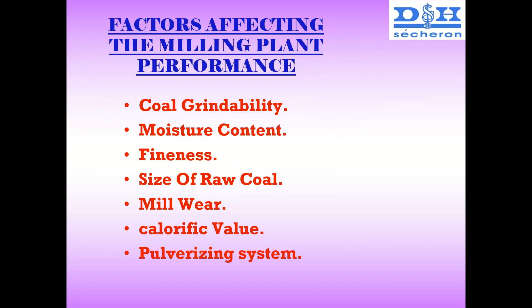The factors that affect milling plant performance are: coal grindability, moisture content, fineness, size of the raw coal, mill wear, calorific value, and of course the type and quality of coal. The pulverizing system also plays a role.